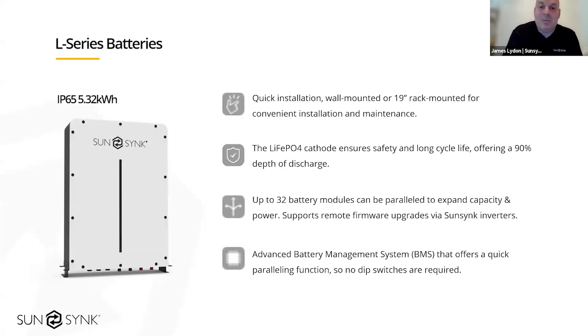So yeah, really scalable. All of our batteries have full advanced BMS software built in. What that's doing is constantly monitoring the individual cell voltages. It's protecting the batteries if there's a setting that's been programmed in the inverter which the batteries aren't happy with. It's constantly monitoring everything: temperature, battery voltage, individual cell voltage, and that's essentially looking after the battery.